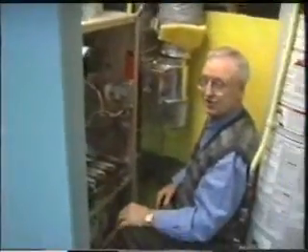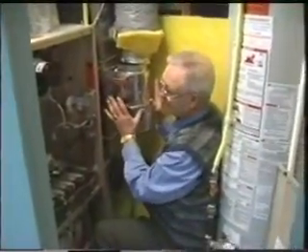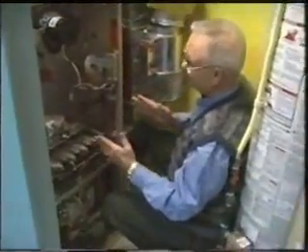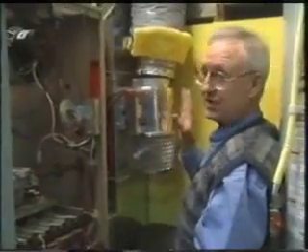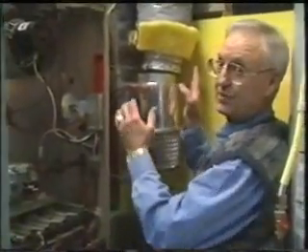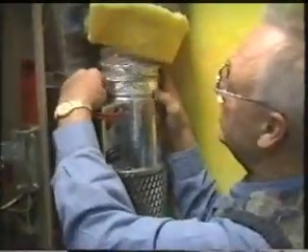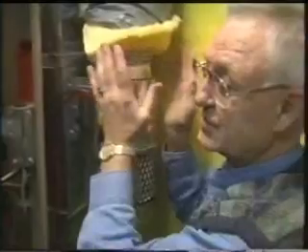Here's the Hoyme damper installed. As you see, it's mounted within a foot above the burner level, and it's also mounted within 2 feet horizontally from the burner level. After the installer installs it, of course, he merely pulls the duct over the top and then fastens it with a nylon band, and then, of course, pulls the insulation over and then seals it with duct tape.